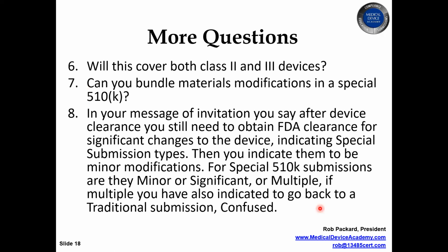But if that were my plan, if I were going to change the materials, and I was going to affect the mechanical performance, and I was going to redo the verification, I'd want to submit a pre-sub and make sure the FDA was okay with that approach. But I think that's exactly what the example I'm going to present did.